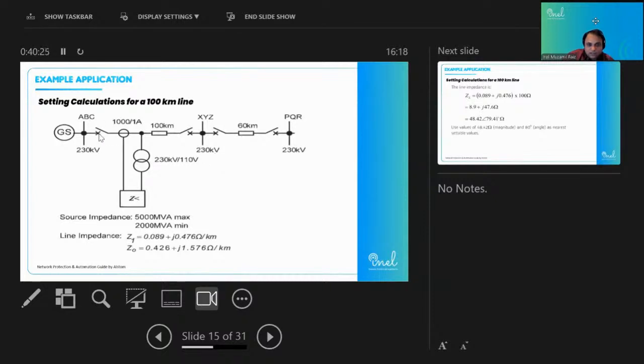That's why this relay protects 85% of this line section with zone 1. With zone 2, it is 120 or 135% of the next line, so it is protecting the whole of this main line and some portion of the next. But it should have some delay, because if the fault is at this location, then this portion should be isolated by this relay, not by this relay. So zone 2 will have 300 millisecond time and zone 3 will have 700 millisecond time. For this relay, its prime responsibility is this section of the line. This relay will give backup protection to this PQR section, and this ABC relay will give backup protection to this portion and also this portion.